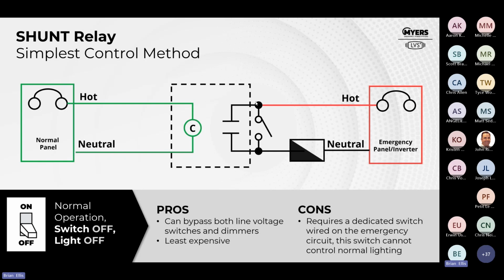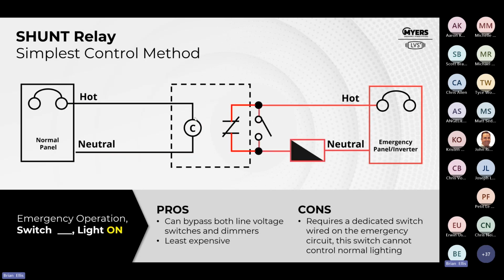Then we bring the emergency, run it through this relay out to the emergency fixture, and you put your switch or your lighting control device right here. So it's always on the emergency switch leg. You can see this switch can never power any normal lights over here because they're not connected to it. This is the reason the shunt relay can only turn on and off emergency fixtures. They cannot turn on and off normal fixtures. So this allows you to get your normal light on and off. And when utility goes away, when power goes away on the coil of a normally closed relay, what happens? It closes, providing an alternate, or a shunt, around the control device. So this fixture will be on in loss of normal power.